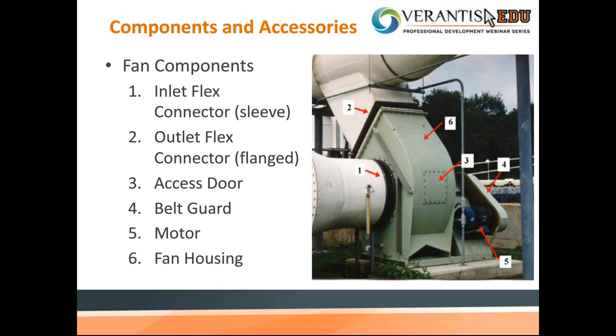The difference between these two is that number 1 is a slip fit style flex connector, which will connect plain round duct with a plain round inlet, and these are held together with stainless steel adjustment bands. Number 2, which is a rectangular outlet flex connector in this case, is flanged, so it'll attach to flanged duct as well as the flanged outlet of the fan. Yes, you can do flanged inlets. Yes, you can do plain round outlets. You can do all sorts of different types of flex connector arrangements. This picture just shows the difference between the two.